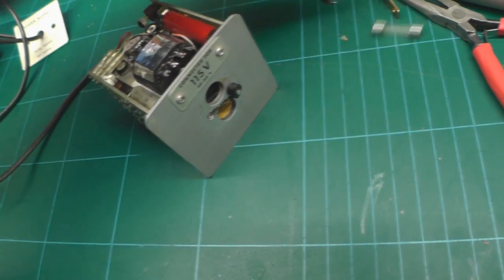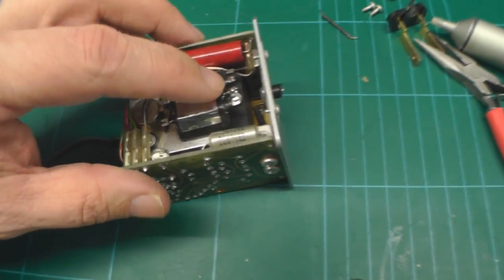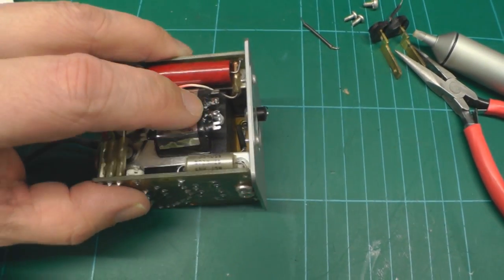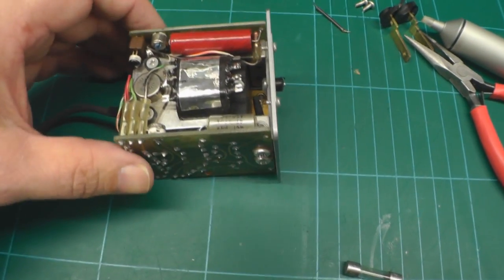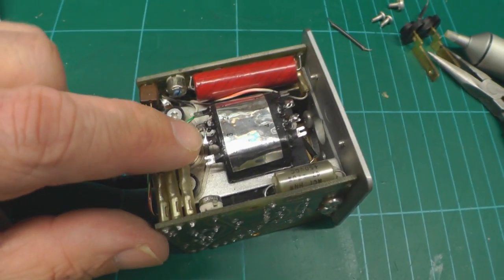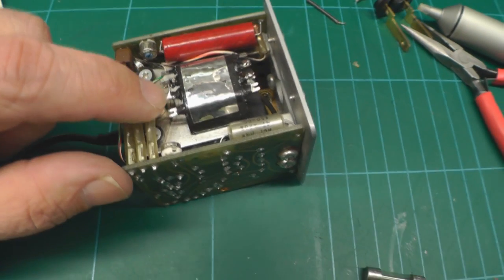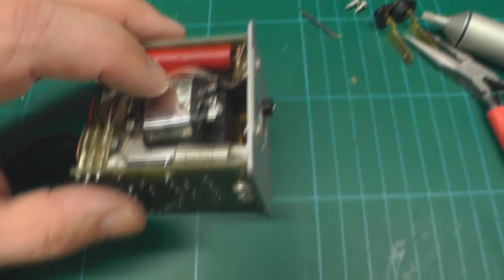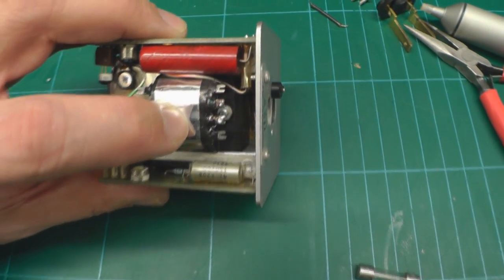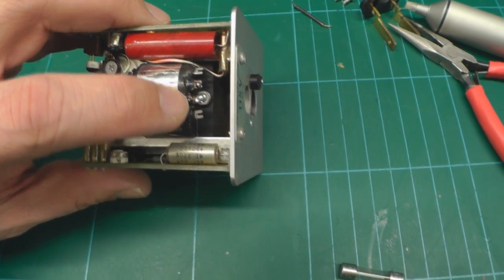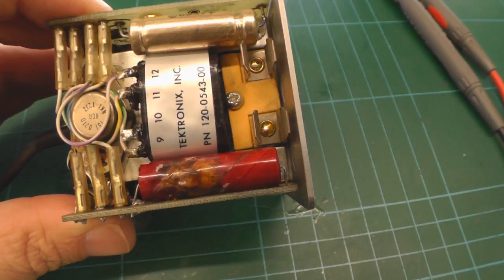Okay, I've disconnected the 110 volt plug, and I've removed the primary wiring that was up onto the transformer there, and I've linked out the two coils on the primary side. So there's two soldered connections there on terminals 1 and 4. That's basically my live and neutral input there.